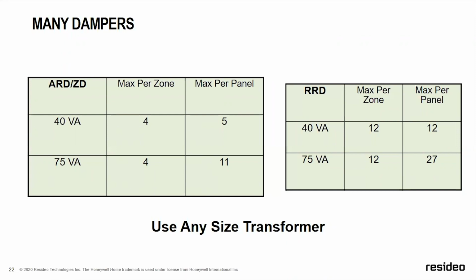You see on the right side, the RRDs, which is retro round damper, you can use 12 per zone with a 40 VA. You can only use 12 per zone with a 75 VA, but if you do the math there, max per panel is more than double. The reason for this is an RRD is a 3-wire instead of a 2-wire, requires less VA to drive the motor.